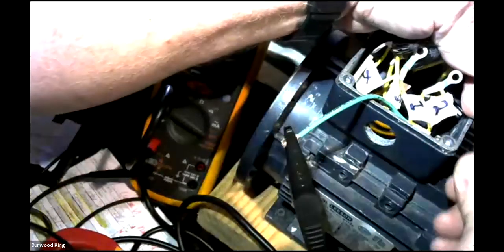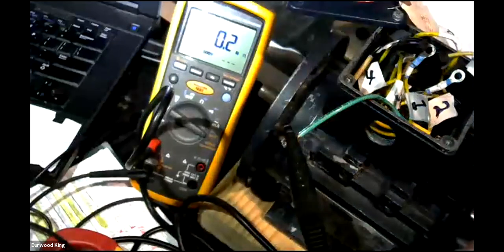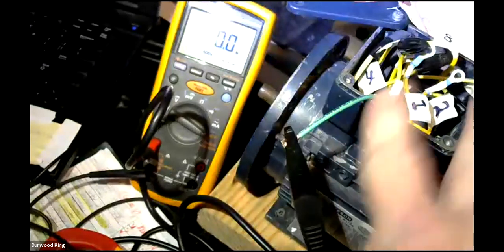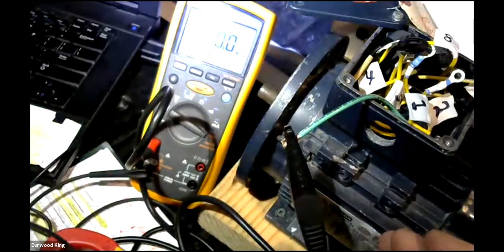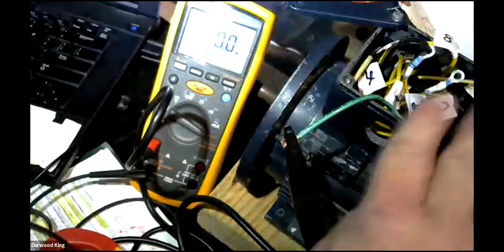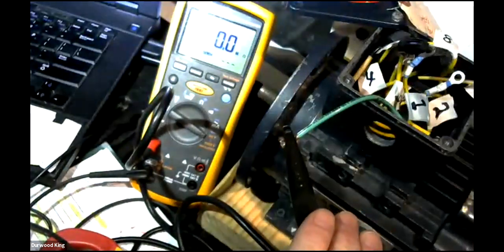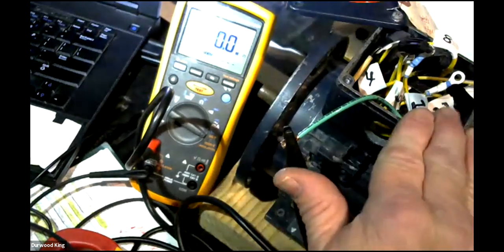Okay, let's systematically step through this now. You saw that phase 2 read 0.2 megohms, right? Now let's go to phase 3. Phase 3, now watch. It's reading 0. You see that? That's hardcore short. Now, so we're checking each leg to ground. Now, your other test, this tells you, do you have a winding shorted to ground? Okay. What it doesn't tell you is, do you have a broken winding, like an open winding that's actually broken in two inside the motor?